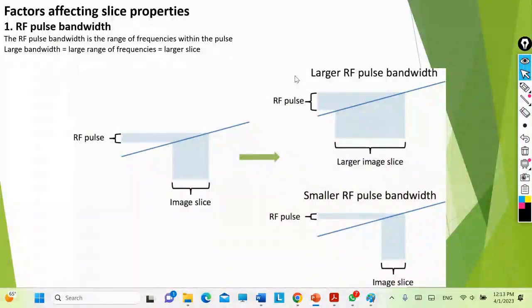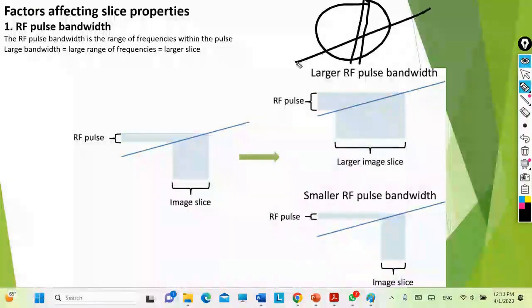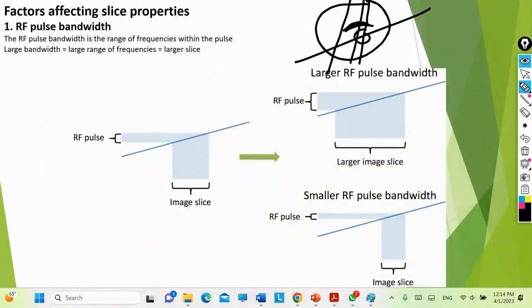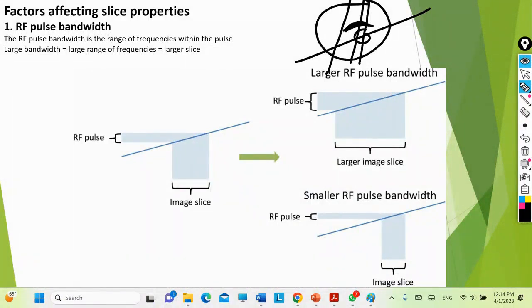The RF pulse you send to the organ has a range of frequencies — you don't provide a single frequency but a set of frequencies that includes the slice you want to take. The larger the thickness of the slice, the more frequencies are present within it. If you increase the thickness, you increase the amount of frequencies present, so you need to provide an RF pulse with a larger bandwidth. This is called the transmitter bandwidth, and it increases with slice thickness.